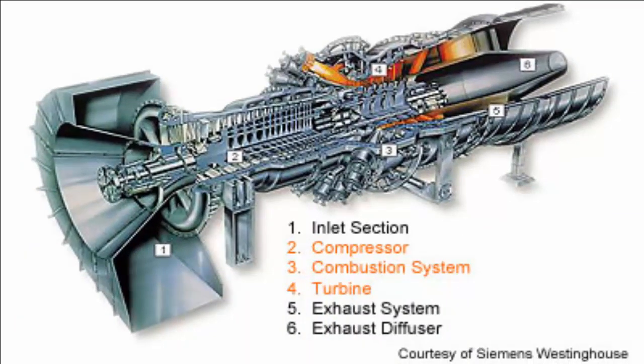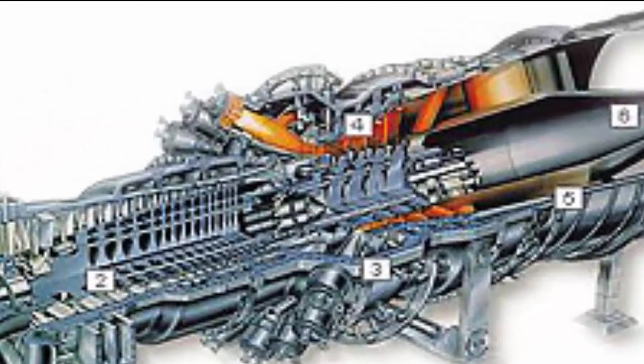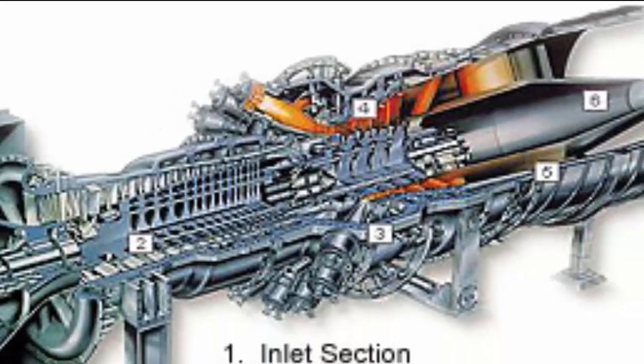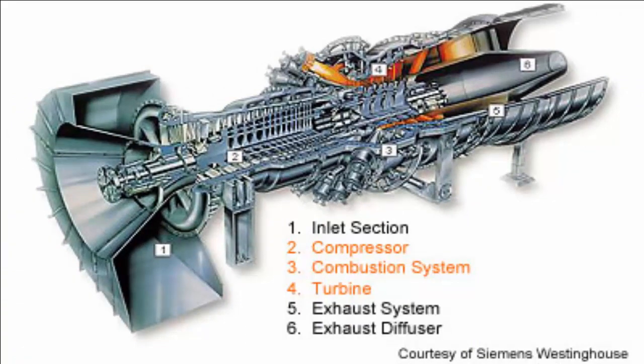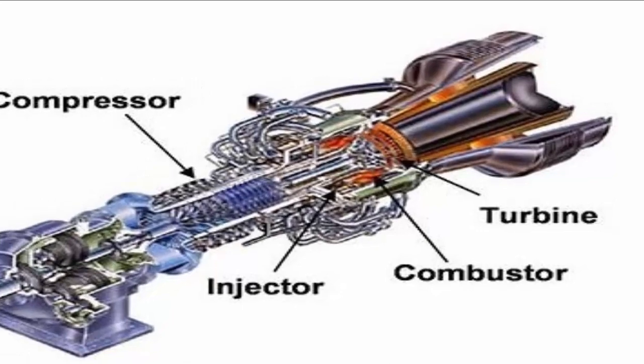The combustion produces a high-temperature, high-pressure gas stream that enters and expands through the turbine section. The turbine is an intricate array of alternate stationary and rotating airfoil section blades. As hot combustion gas expands through the turbine, it spins the rotating blades. The rotating blades perform a dual function: they drive the compressor to draw more pressurized air into the combustion section, and they spin a generator to produce electricity.